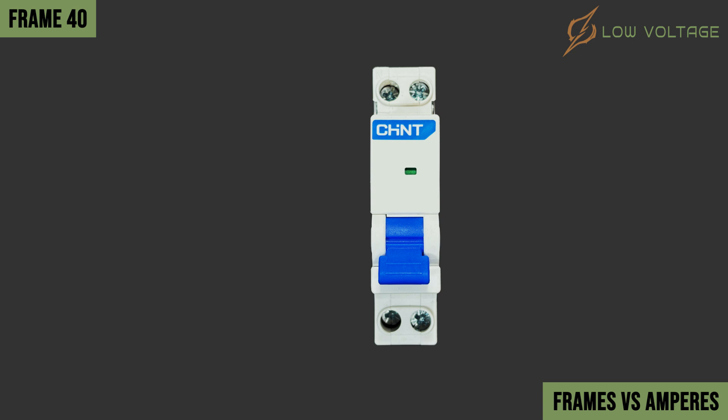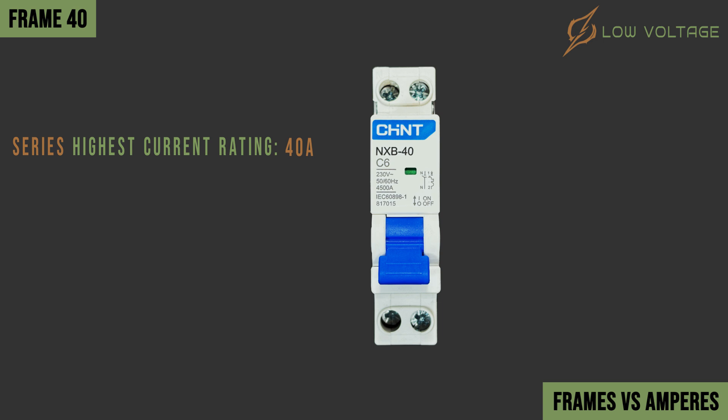Let's start with Frame 40. Manufacturers refer the frame to either a number or a series code and print it on the MCB. In this particular case, the printed frame is 40. This indicates that the highest current rating in this MCB series is 40 amperes. All breakers have a printed current rating to determine its protection characteristics — this breaker has a current rating of 6 amperes. Another example within the same 40 amperes frame but with a different rating: this MCB has a current rating of 40 amperes.